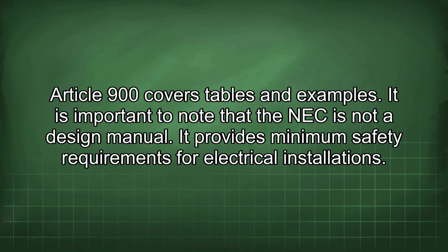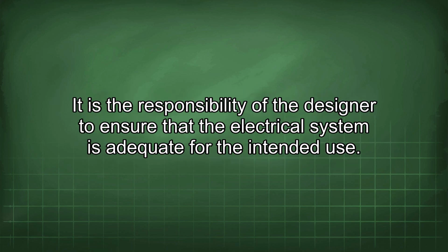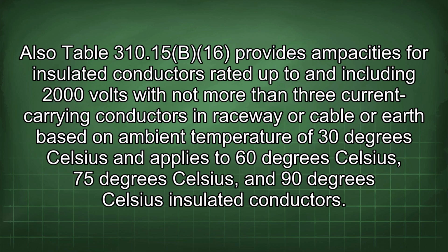It is important to note that the NEC is not a design manual. It provides minimum safety requirements for electrical installations. It is the responsibility of the designer to ensure that the electrical system is adequate for the intended use. Also, Table 310.15(B)(16) provides ampacities for insulated conductors rated up to and including 2000 volts with not more than 3 current-carrying conductors in raceway or cable or earth, based on an ambient temperature of 30 degrees Celsius, and applies to 60 degrees Celsius, 75 degrees Celsius, and 90 degrees Celsius insulated conductors.